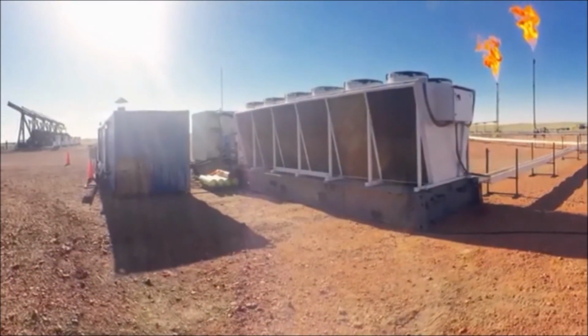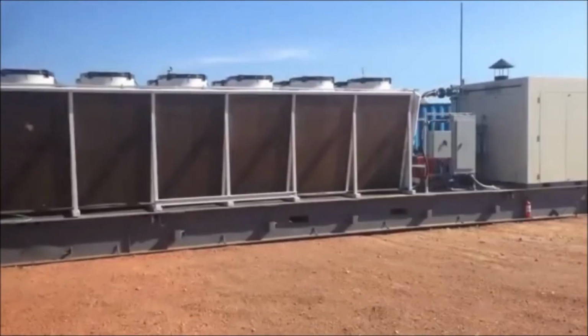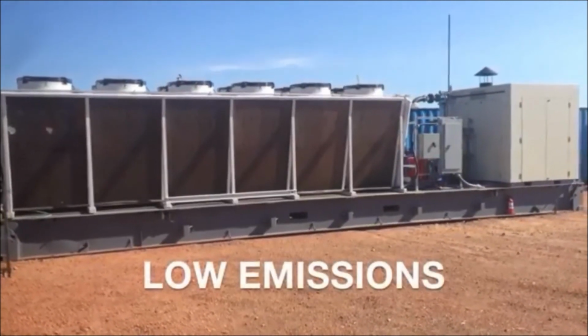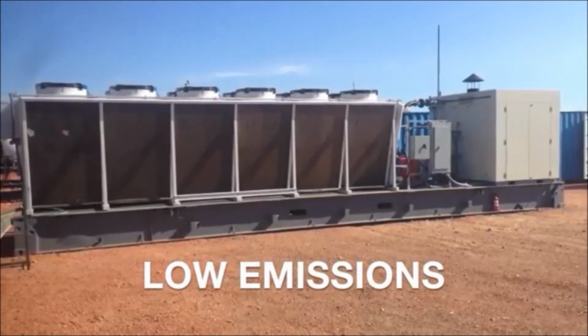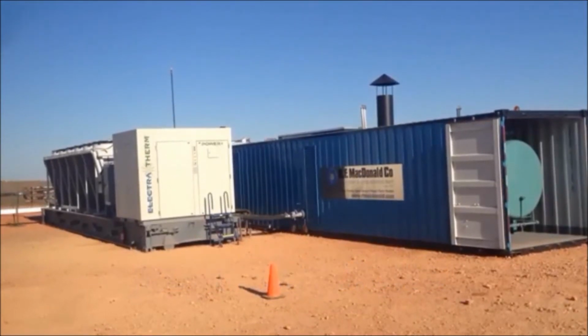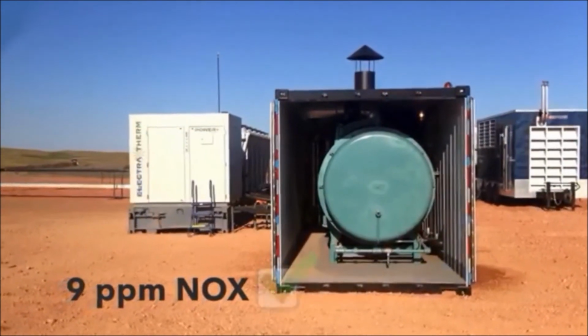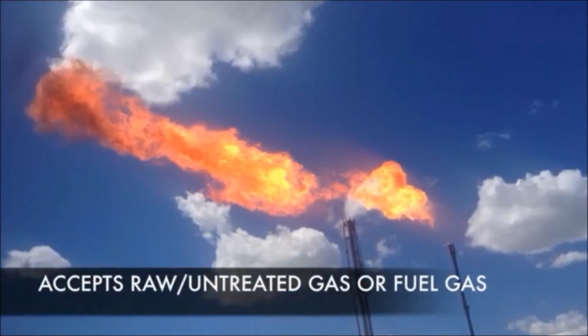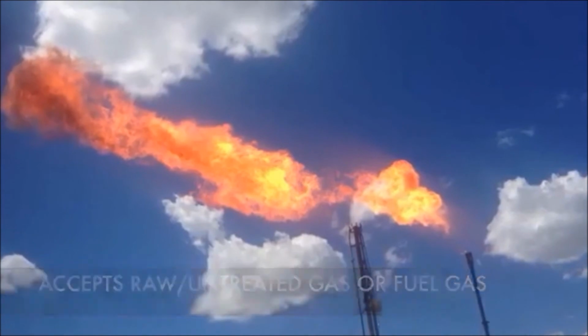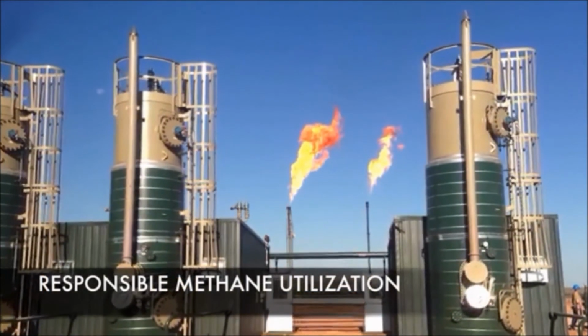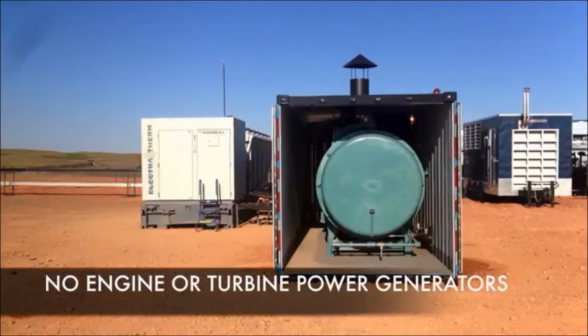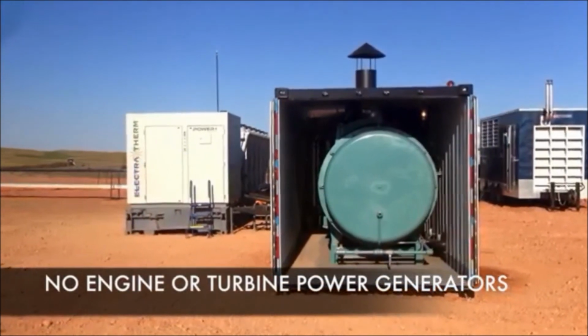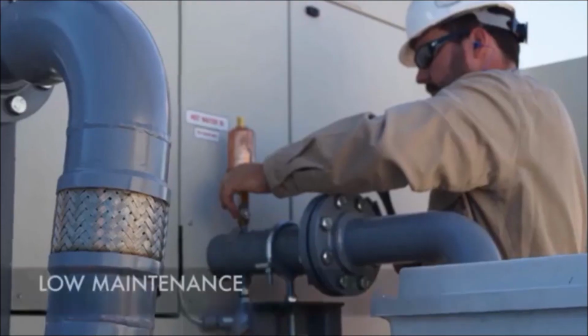The boiler precisely controls the fuel-to-air mixture, ensuring clean combustion that results in very low emissions, especially compared to typical on-site generation equipment such as a reciprocating engine. 9 ppm NOx is easily achievable. Additional benefits include accepts raw and untreated gas or fuel gas, provides responsible methane utilization, no capital-intensive engine or turbine-powered generators, and low maintenance.